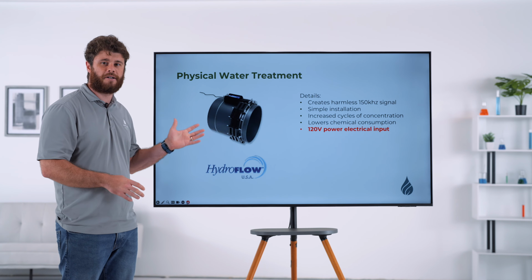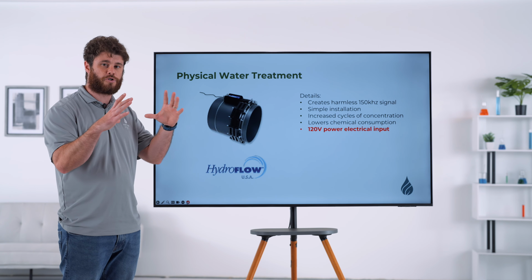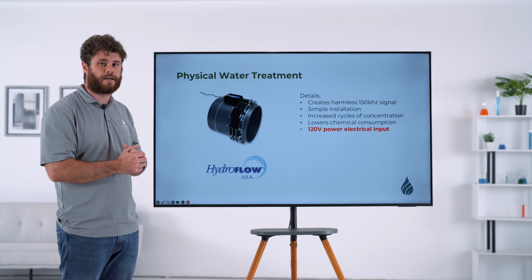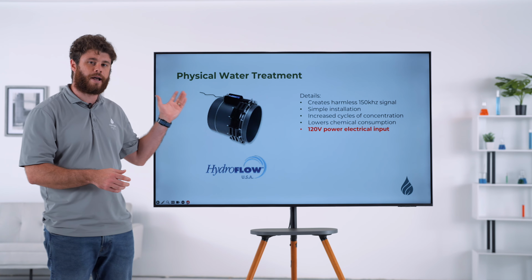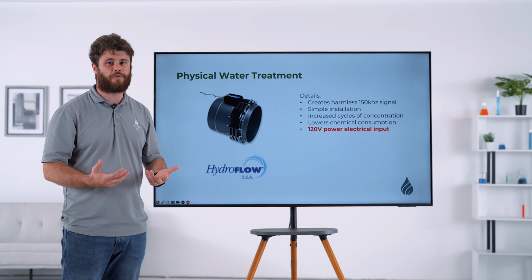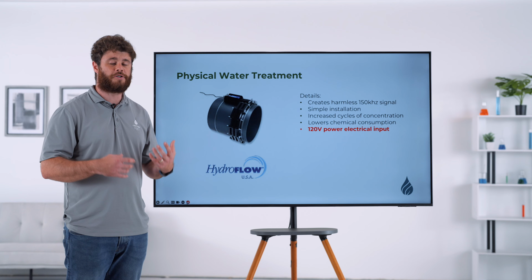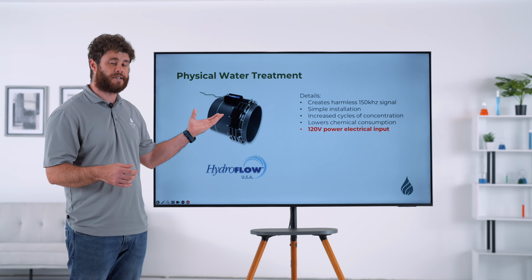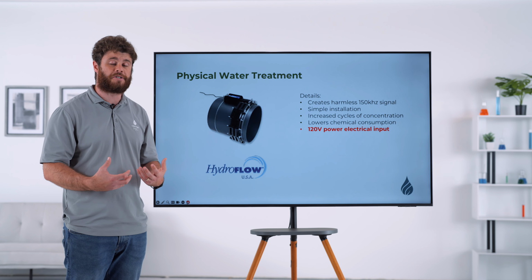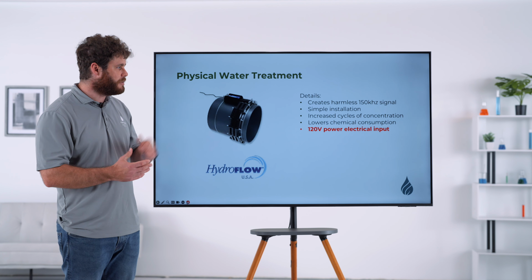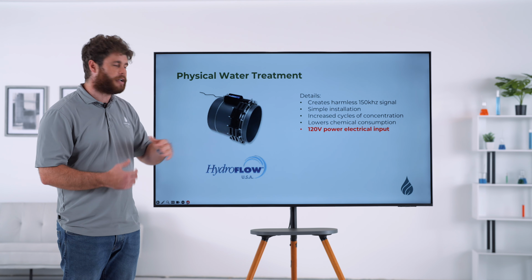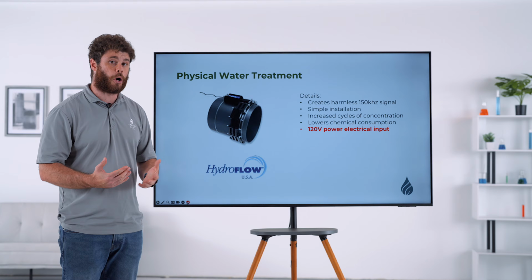So this device gets mounted on the outside diameter of your pipe through structural supports, so you don't have to cut into any piping, and you simply plug it into a 120 volt outlet in the wall, and it acts just like a transformer. But instead of stepping down a voltage from a primary to a secondary transformer, this device steps down the voltage from the primary transformer, the Hydroflow itself, to the secondary transformer, which is actually the water in the system. It's a very simple installation, increases cycles of concentration to typically double what you're currently getting, but with significantly reduced chemicals, typically 20% of what you were just using.